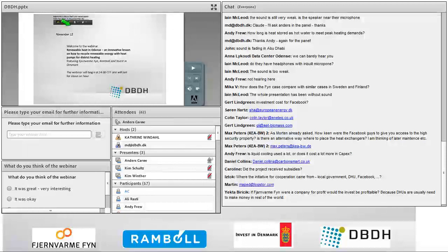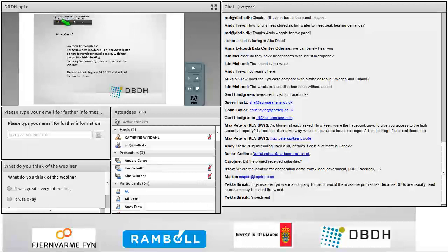Go ahead. Well, I think from a technical point of view, it's important to focus a lot on the temperatures in the system and reduce that lift as much as possible by decreasing the temperature in the district heating system and increasing it on the chilled water side, and also to have this discussion about security of supply. How do you plan on operating the waste heat recovery system? What sort of procedures do you need to have if there is a failure at the heat pump plant? How can the data center cope with that? I think that's some of the key aspects in the early phase of a project like that.